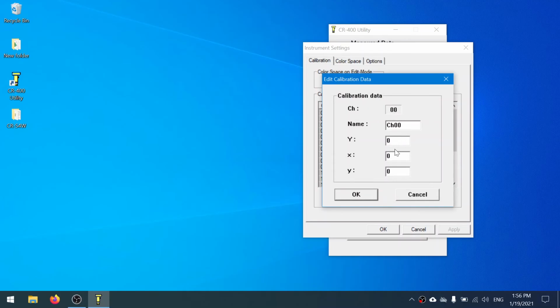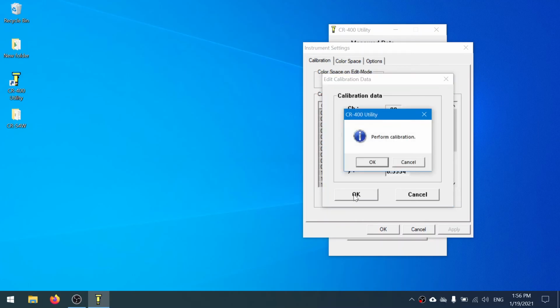Leave this as default, but for this XY values based on the white plate earlier, which I showed you, you have to key in the value for the D65. So in my case, it is 93.7, 0.3170, and 0.3334. So these values would be based on the equipment, based on the white calibration that you have.